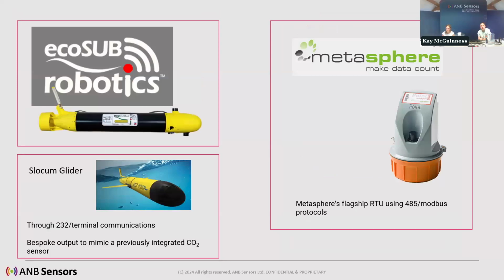With EcoSub, we put the sensor onto the EcoSub system, showing the miniaturizability of the sensor. With Metasphere, we have it on their RTU through our 485 Modbus protocols. And we can integrate onto a Slocum glider. We've written special firmware outputs which mimic that of a previously integrated CO2 sensor, whereas instead of providing CO2, we actually give pH in the output stream. This is through a 232 terminal communication program, and that's available on our version 9 firmware now. So hopefully this shows you that it's very easy to integrate.